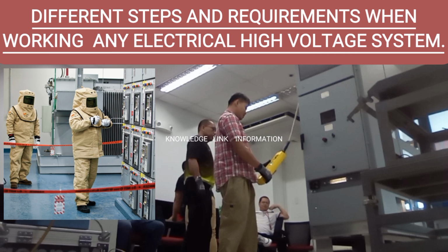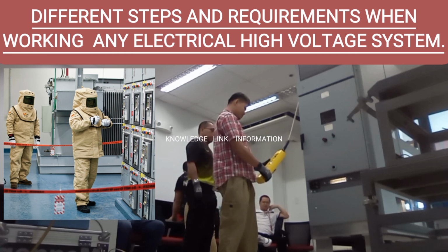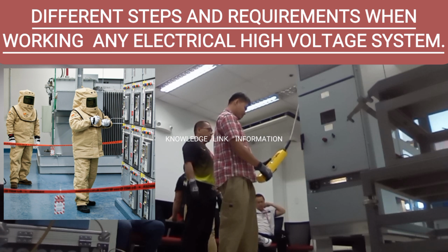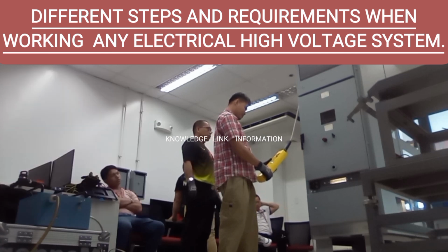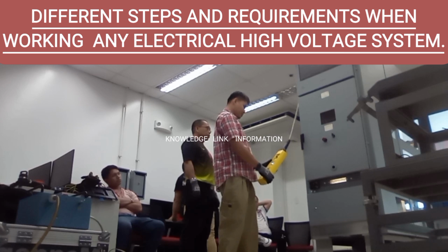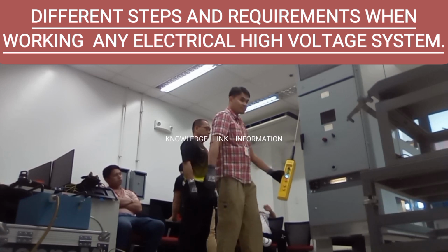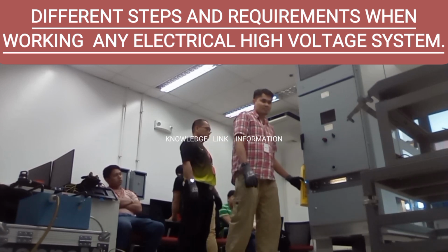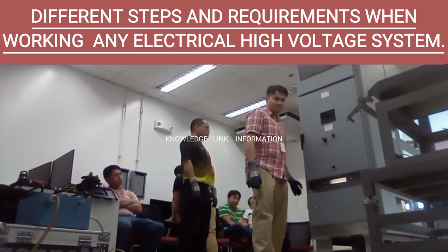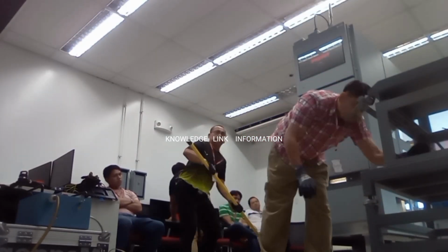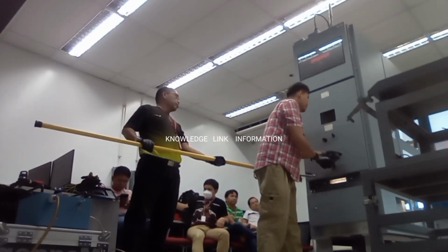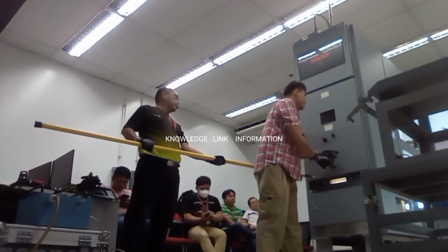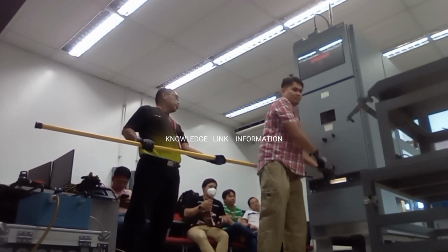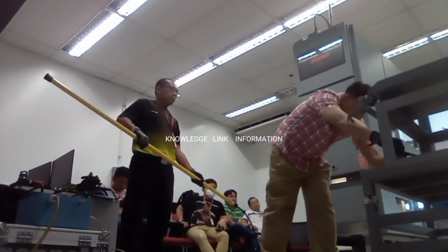But we are not wearing any approved high-voltage suits in this video, because it is only a school activity without high-voltage presence. Number 3. Press the off push button to switch off the high-voltage circuit breaker from the power source inside the switchboard. Number 4. Take special tools to rack out the high-voltage circuit breaker for breaker isolation out from the bus bar.